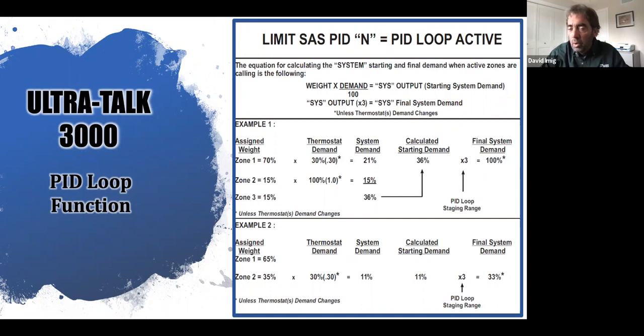In this case, I've got zone 2 calling as well. Now, zone 2 weight is 15%. My demand in that area is 100. Now, you'll see 100 for 2 reasons. One is, like I mentioned, we've got a communicating thermostat, and we've got a large degree of setback, which would be somewhat ridiculous, but that could give you 100% demand. But in most cases, you will see 100% demand because that is a non-communicating thermostat. A non-communicating heat-cool thermostat can only give you 100% or 0%. It does not give you the information, the demand based on the set point and or the temperature it's trying to achieve. It gives you on or off, 100%.